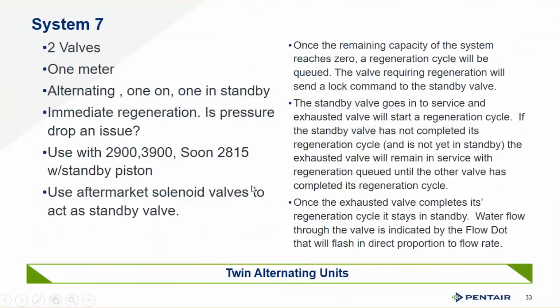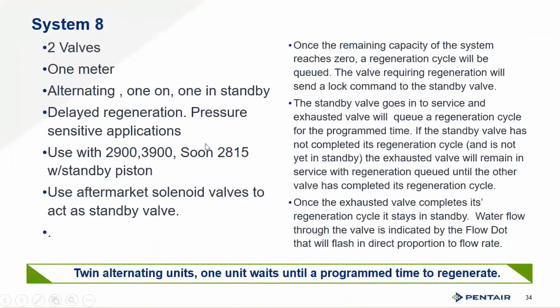System 7, this is two valves alternating back and forth. This is for alternating tanks, bringing one into service while the other one goes offline to regenerate, back and forth. This is for constant demand of soft water in lower volume flow rates. System 8 is the same as a System 7, but the regeneration is left until later so that we don't impact water pressure during operation of equipment.